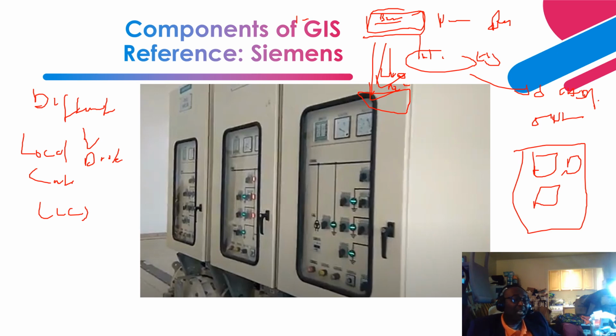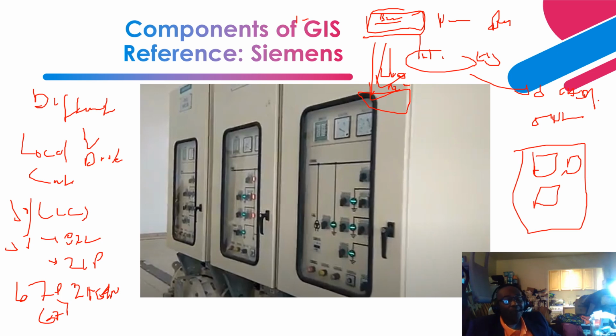Okay, so for the line side, you have a differential protection, 87L. Then you have your distance, right? You can have your distance phase and distance ground or neutral, right? Then sometimes you can have a directional phase and directional neutral, in 50, 51, instantaneous overcurrent and time overcurrent on these feeders. Right? Okay, so as you can see over here, on the line local control cabinet, these are the metering indications that tell you your voltage and your current, right?